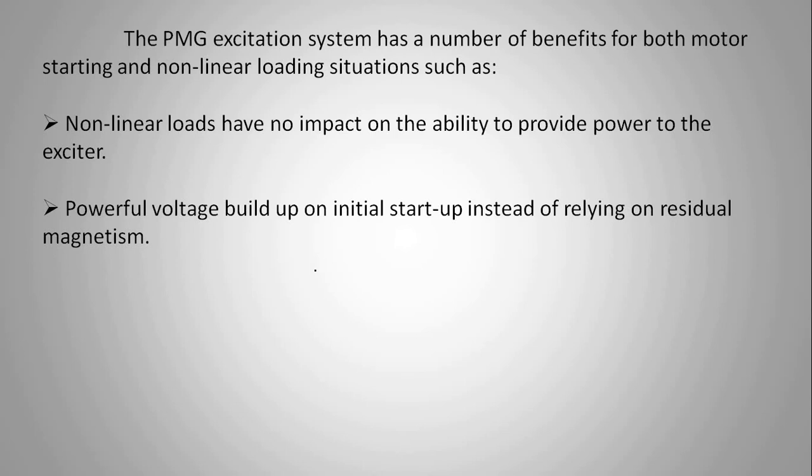We can have a powerful build-up voltage at the initial startup condition instead of relying on residual magnetism. If you go for self-excitation instead of PMG excitation, you need residual magnetism. If there is no residual magnetism, there will be no voltage buildup in self-excited alternators.